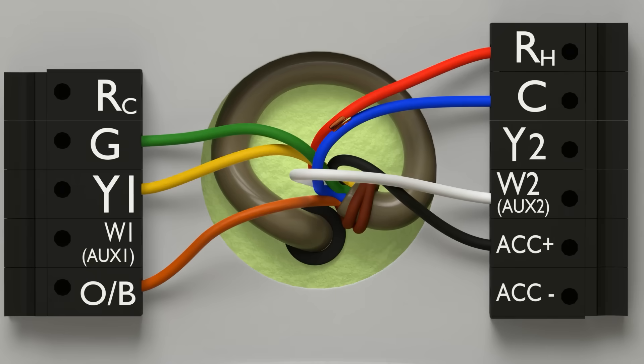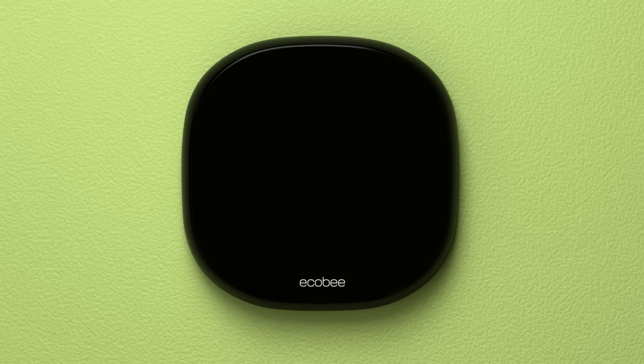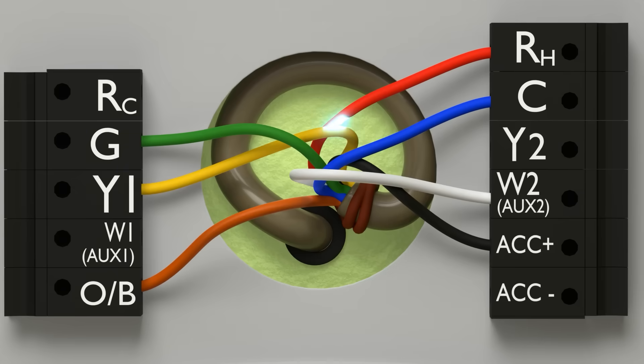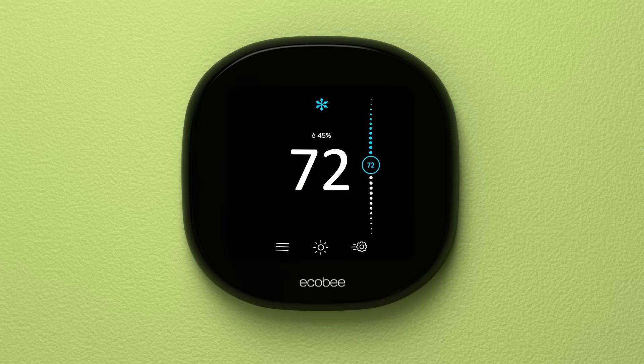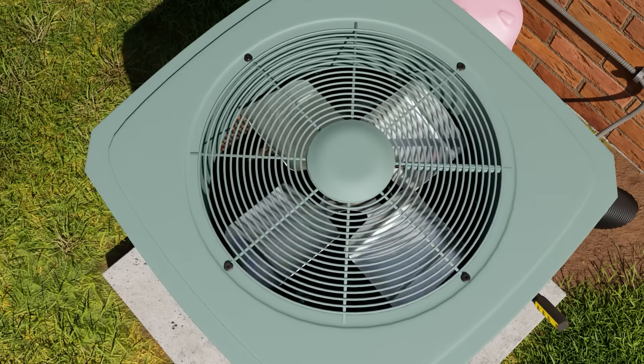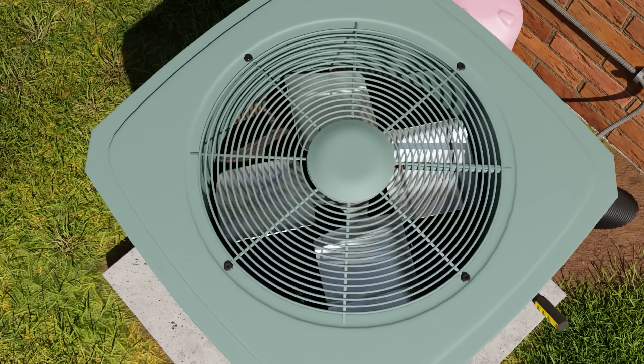Here we show another type of dead short from hot to common, resulting in a blown fuse and a blank thermostat. Here we show a connection between two energized circuits, red and switch leg yellow, going to the contactor. In this case, the red will power the yellow all the time, and the system will run constantly.